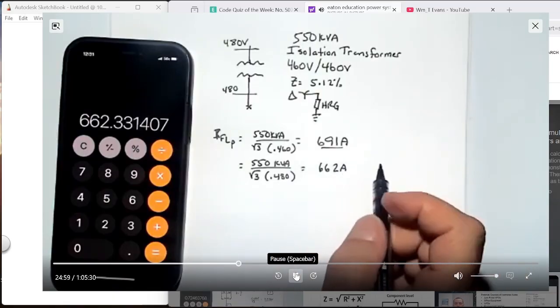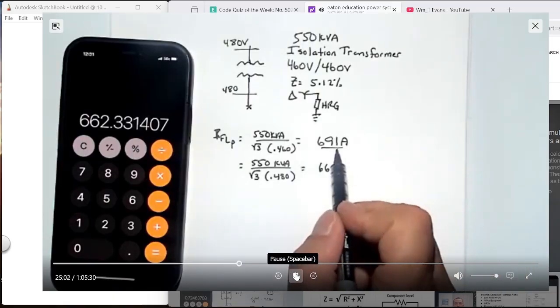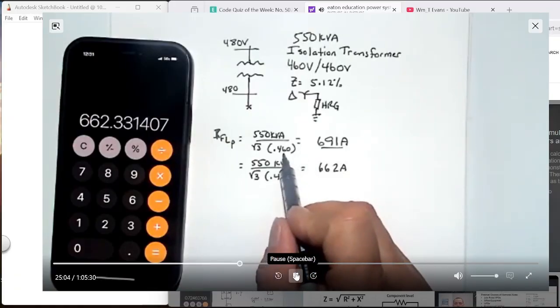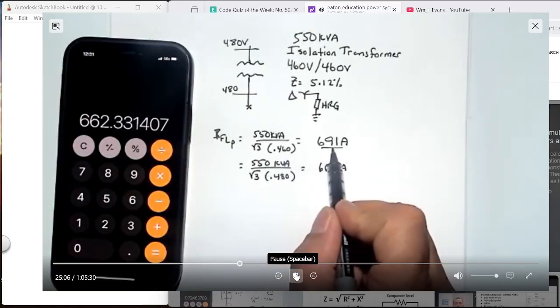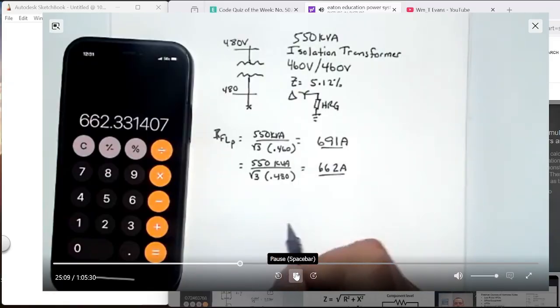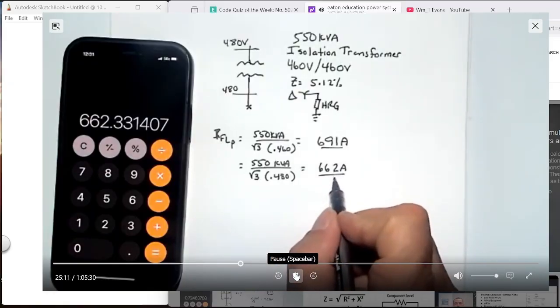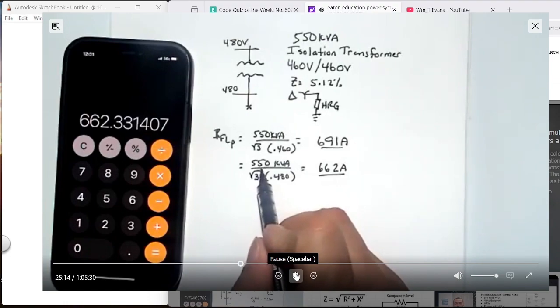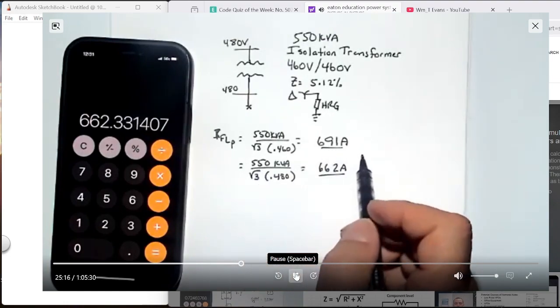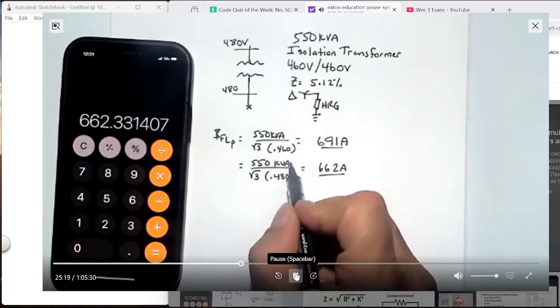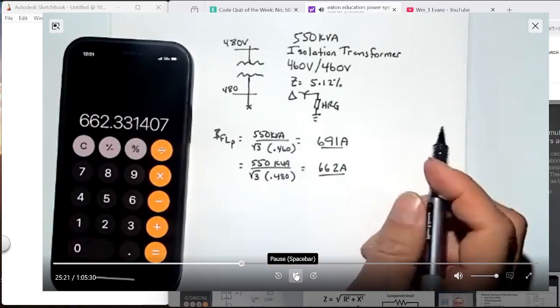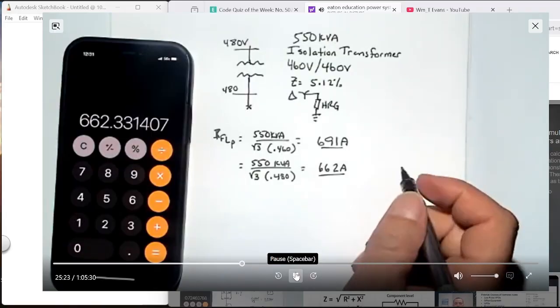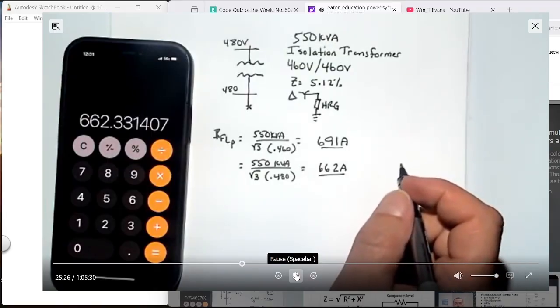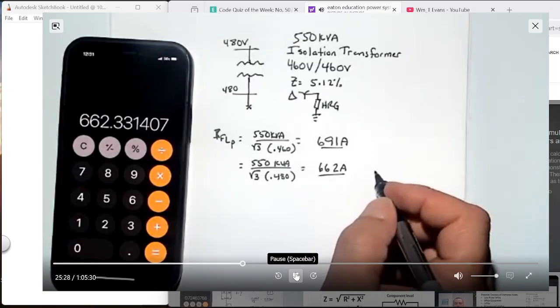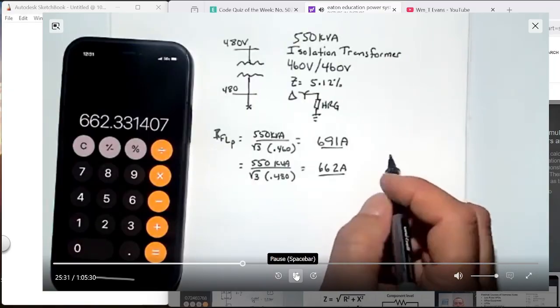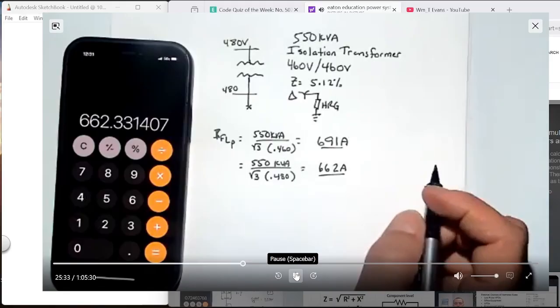But what you have to remember is kVA is a capacity thing. It's volts and amps together. So if we run at a lower voltage, we could go up to that amp capacity rating. If we run at a higher voltage, we're likely going to only want to put up to that many amps through it. Otherwise, we're going to exceed the kVA rating of the transformer. So that's why these two numbers are important to understand. Most of the time, you'll see motors rated at 460. You'll see transformers rated at 460. A lot of times that's because they're down in the system where you expect the voltage to run somewhere near that level. And so to get the full load capacity out of them, you can use that 460 volt level.